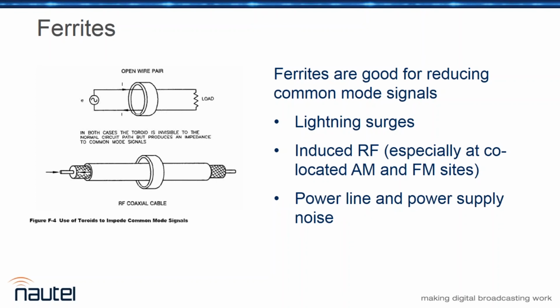So definitely they're a great tool for things like getting rid of induced noise. By the same token, they work just as well on lightning surges, where your surge will tend to be either on the center conductor if you get a tower height strike that, for whatever reason, doesn't go through your ball gaps, or if you happen to have a grounded tower, like a folded unipole, and it got hit, then ground potential is going to spike high. What the ferrite will do when you get current flowing through one side that's unequal or imbalanced to the current on the other side, the ferrite will saturate and attempt to induce an equivalent signal on the opposite conductor. So as long as the net difference between the two stays the same, the risk to the equipment's a whole lot less. All right, on to the next.